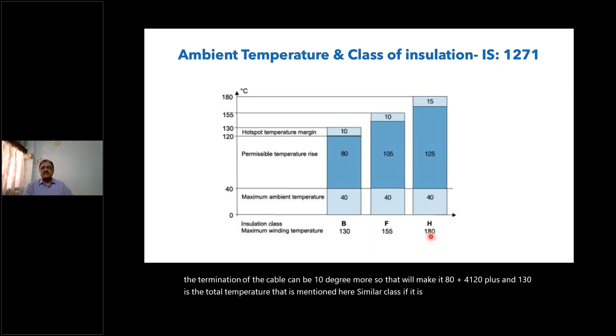So when you have 80 plus 40, some parts which are blocked from insulating current or the blow of the fan can be hotter by 10 degrees centigrade. Some parts which are very close to the termination of the cable can be 10 degrees more. So that will make it 80 plus 40, 120, plus 10, 130 is the total temperature. That's what is mentioned here. Similarly, for class F, it is 155. Class H, it is 180.